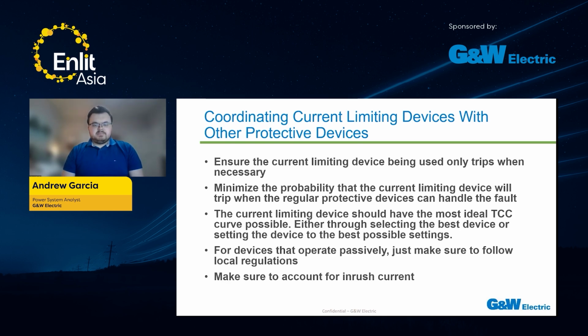For devices that operate passively, just make sure to follow your local regulations. And when I say passively, I'm talking about both the reactor and the solid state breaker. Make sure to account for inrush current. Once again, that's very important. You don't want repeated nuisance trippings because you did not think about inrush current from the very beginning of your project.